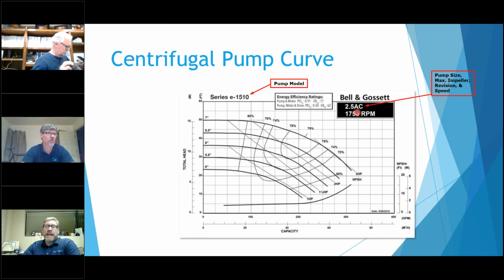It used to be that this first letter, the A's and the B's and the C's, meant a lot to a lot of the manufacturers. The A would be a 7-inch impeller. The B would be 9.5. C, I believe, was 10. You get up to E, I believe that's 11. Every manufacturer used to do it this way. Now most of them have gone to, in this case, a 2.5 by 3 by 7. So they actually list out the discharge nozzle, the suction nozzle, and the max impeller. C is going to be your revision, so this is going to be the third revision of this pump since it was introduced.